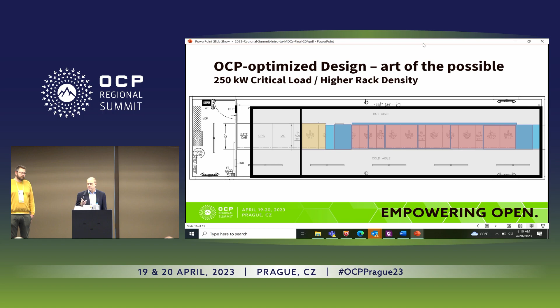If I look at the space, I don't need a UPS anymore, and I don't need as much space in the rear of the rack - just enough for sufficient air flow. I don't need to access from back there, so that space can be minimized. Compared to the traditional build, you could knock out 25% of the volume on this particular instance just by deploying open and driving the density higher. You can almost triple the density of the original solution in 25% less volume. To me, that's the impact - that's impactful. Especially if some of the big OEMs start to offer OCP compliant servers, this stuff will take off like crazy. But from where we are right now, this is where I see the advantages.